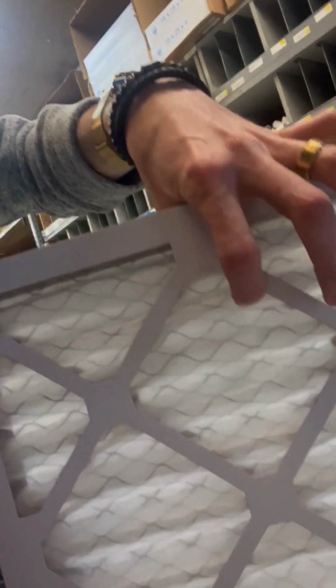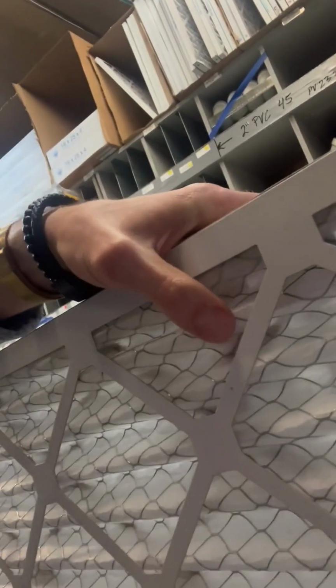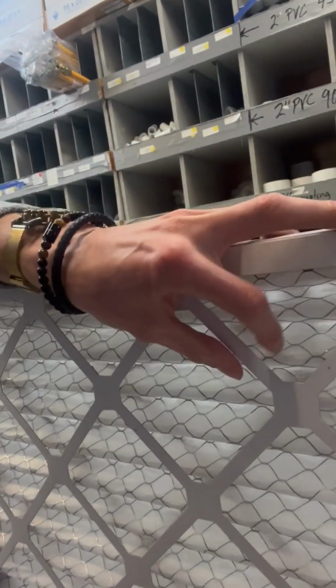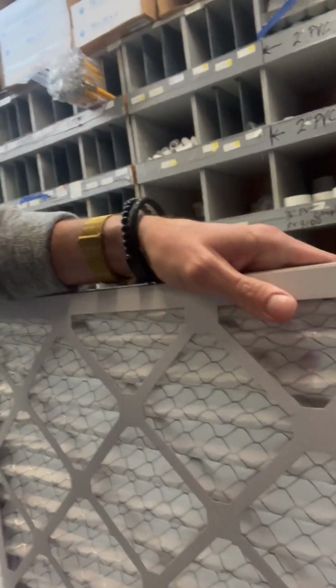So why does airflow direction really matter? This filter collects tons of debris, and as it fills up, it starts blocking airflow. One side just has a bunch of material, while the other side has sharp pieces of wire. Some filters don't have this backing on them, so when it gets too dirty, the filter can completely bow and get sucked into your blower. That can cost upwards of $1,500 to $2,000 in repairs, depending on the type of motor it is. So having the right direction is important.